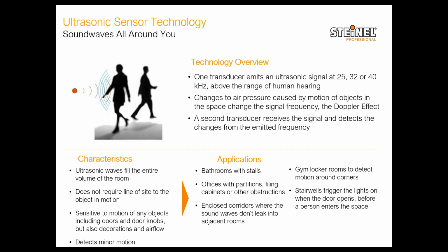Some of the applications for ultrasonic technology are bathrooms with stalls. So this is an easy one. All of us have seen it, that bathrooms with stalls, you don't have line of sight. And you have all these tiled ceilings and tiled walls and tiled floor, which gives you perfect echo, and a simple ultrasonic sensor will pick up everyone who is in those stalls and make sure that the lights don't go off on them.